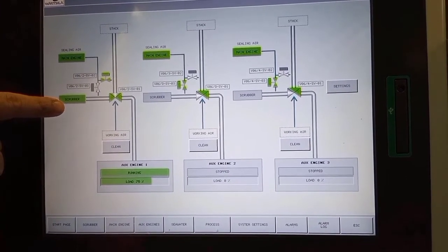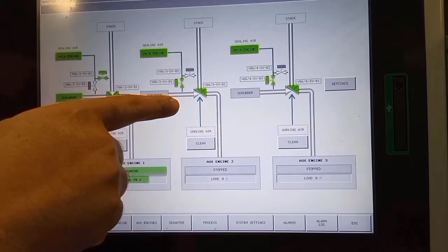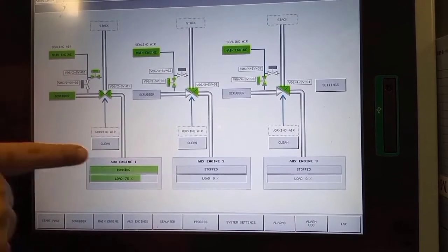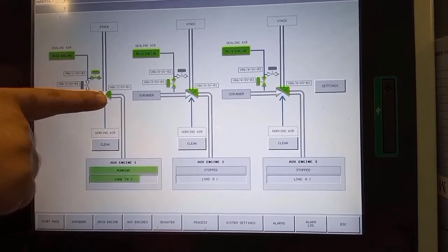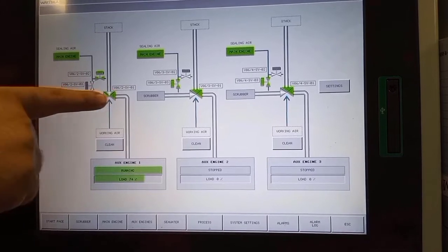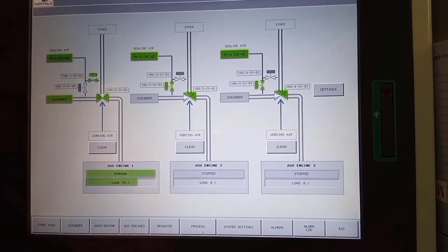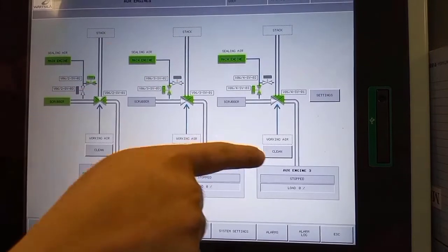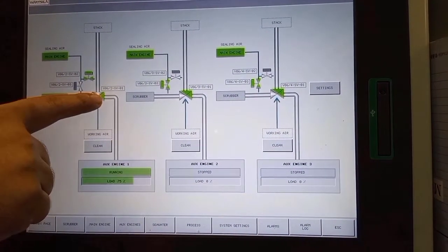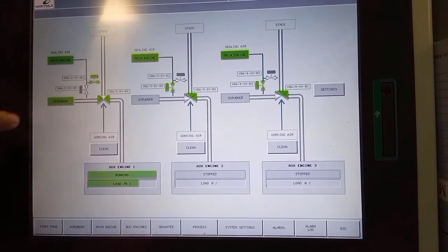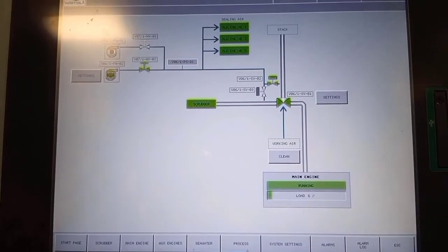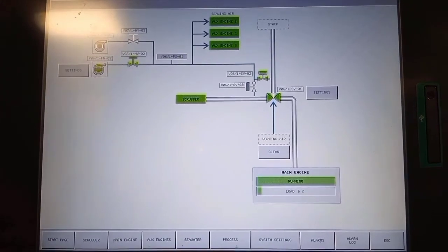In this monitor you can see which generator is under the scrubber system. Currently number one generator is passing through the scrubber; number two and three generators are on standby condition. As you observe, the valve going to the scrubber is closed and the valve going to the exhaust pipe is open.